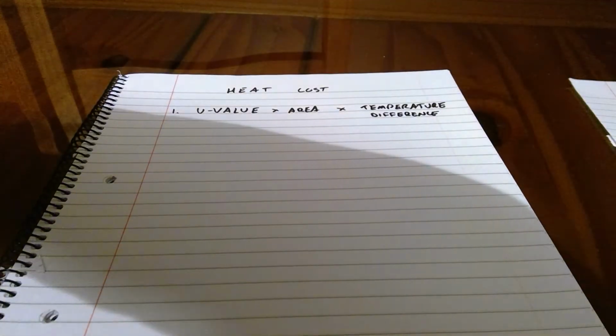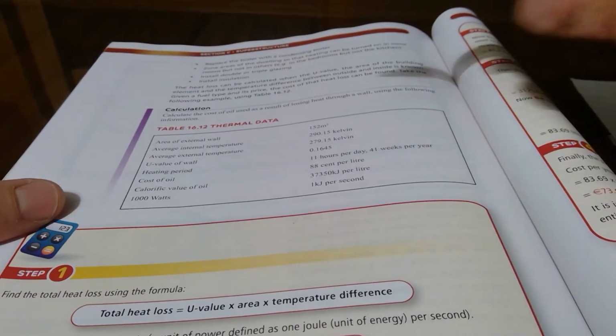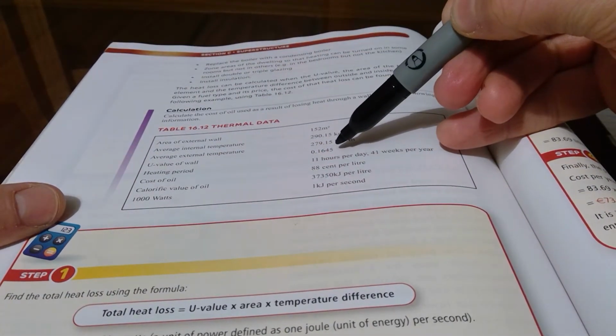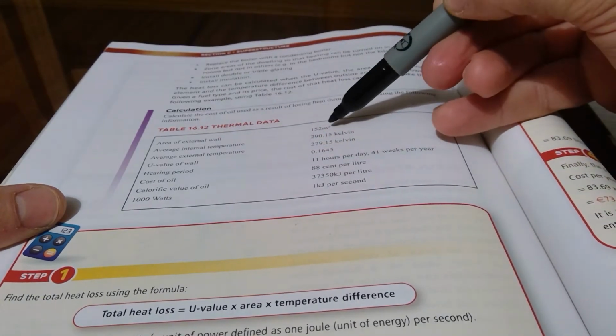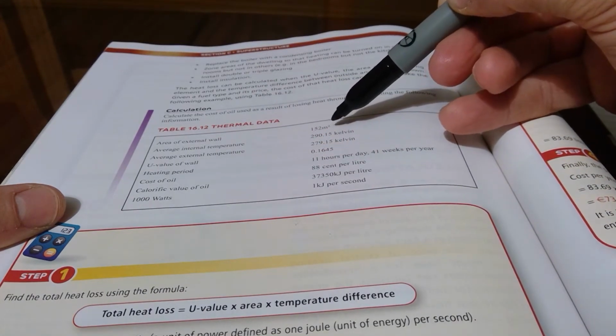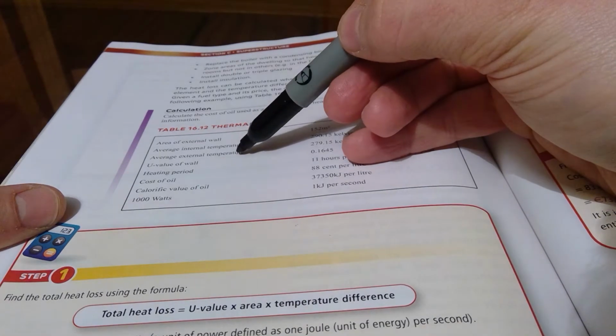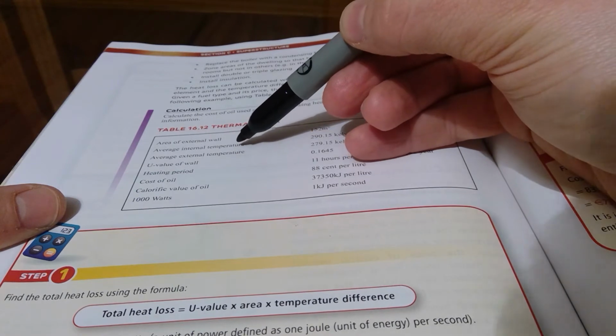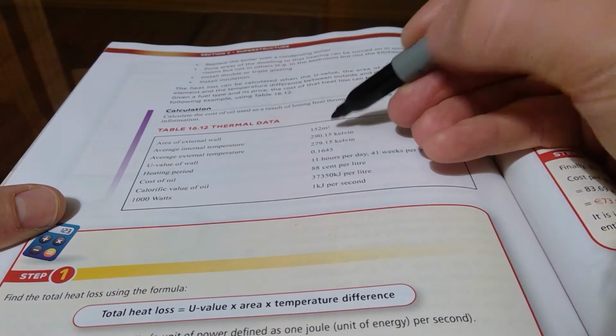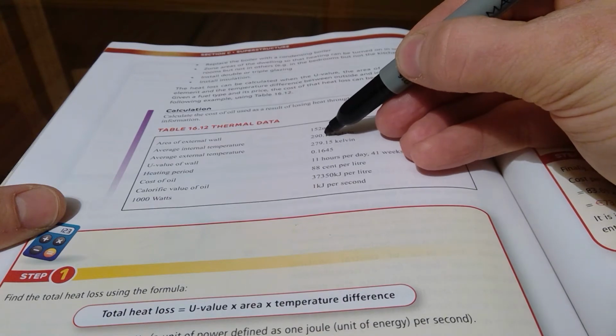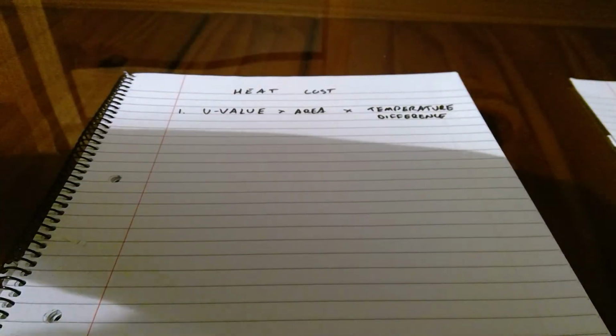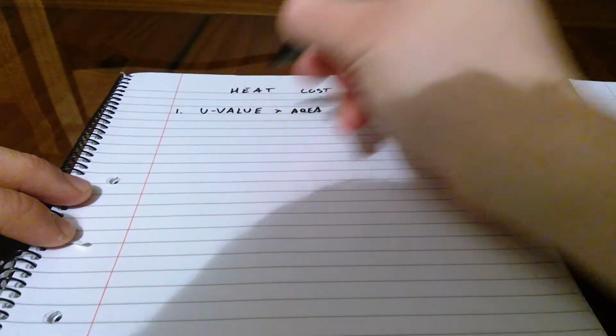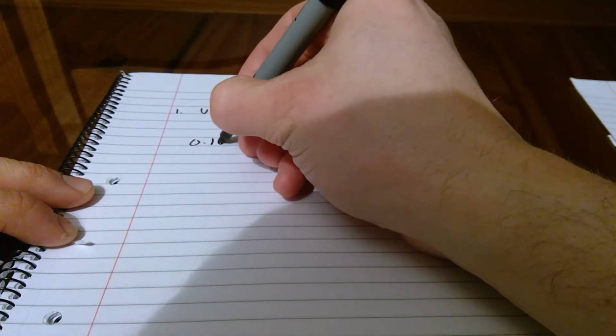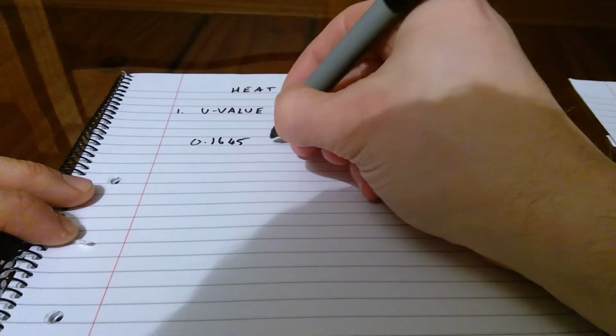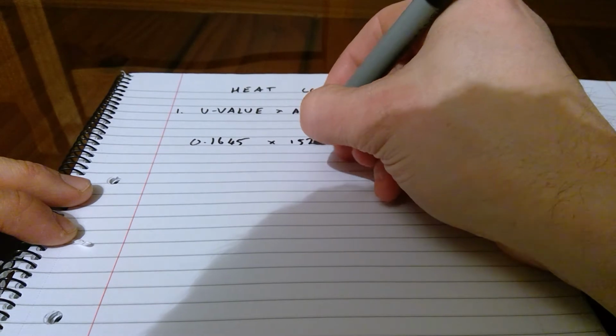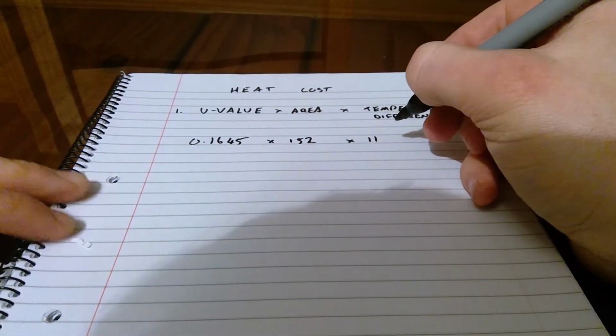Now if we go back over here, we have the U value given to us, 0.1645, the area of the wall given to us, 152, and the temperature difference. That means the difference between the external temperature and the internal temperature, or the outside temperature and the inside temperature. So we basically need to take this away from this to find your temperature difference. A very, very simple calculation. That basically results in 0.1645 multiplied by 152, and that temperature difference works out at 11.